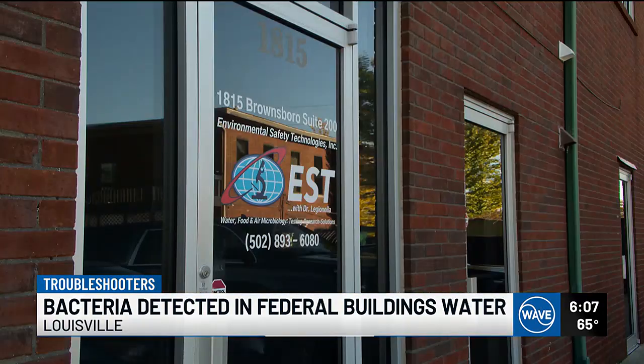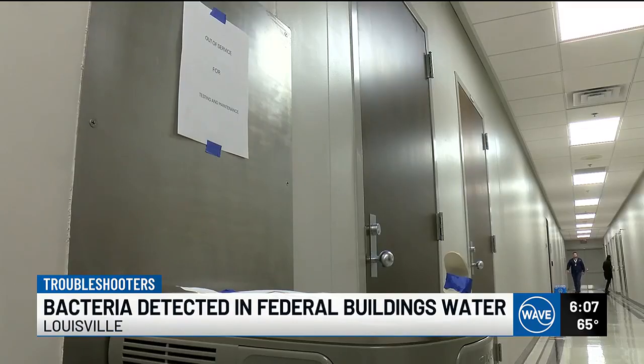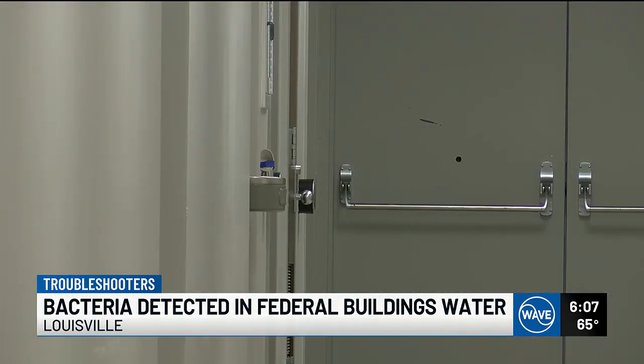George Young helps lead a Louisville lab that's been testing lots of these new government building water samples. It's still prevalent in our water systems, and unfortunately, one of the other side effects of the pandemic was a lot of low usage buildings. And when your building is not used very often, your water is not flushed regularly, you'll develop biofilms, and in those biofilms, the Legionella will proliferate.